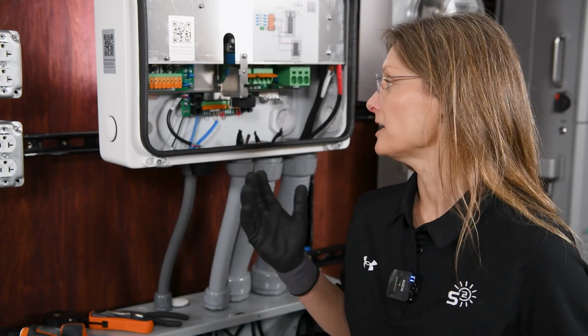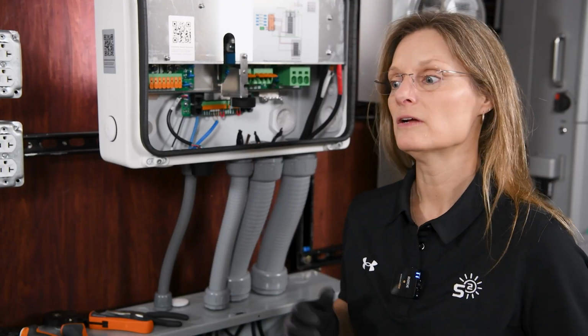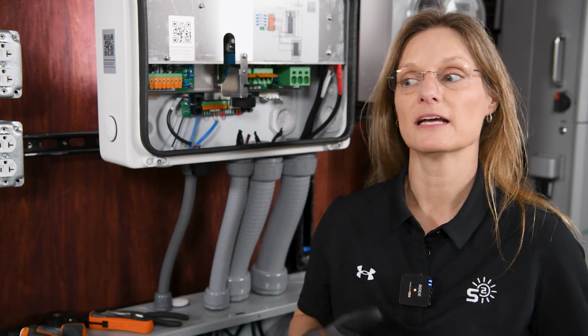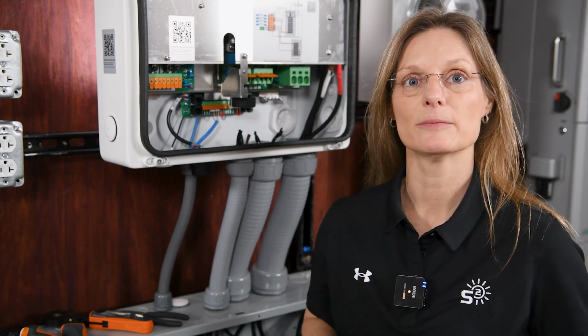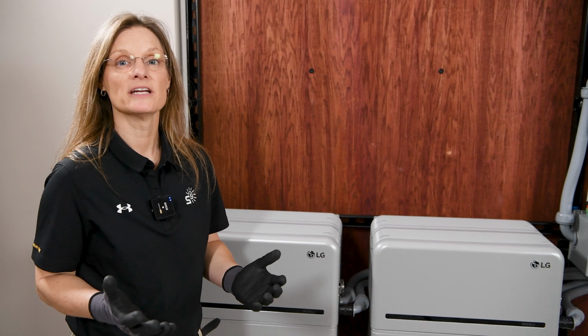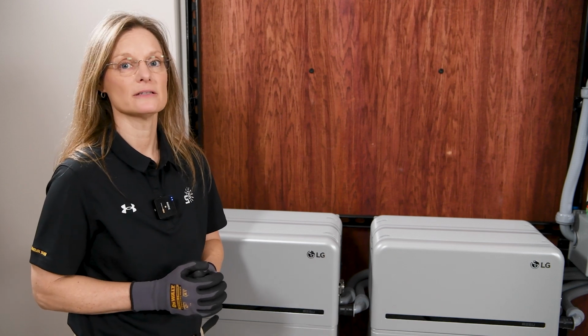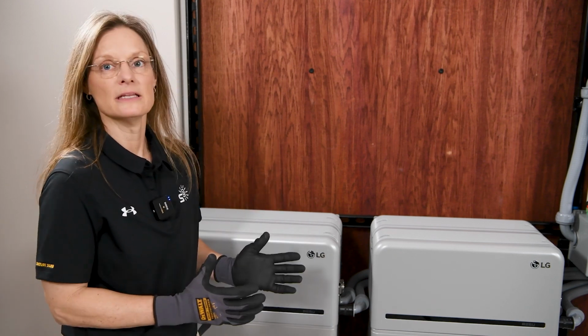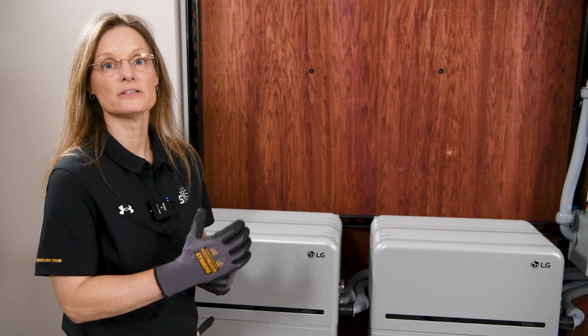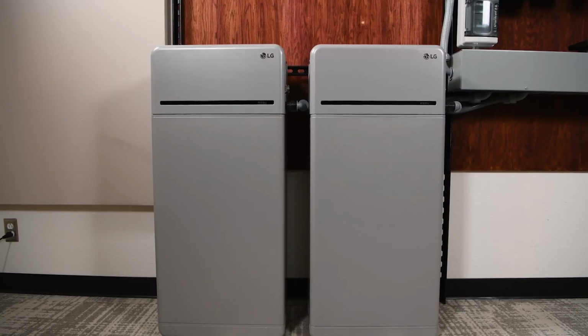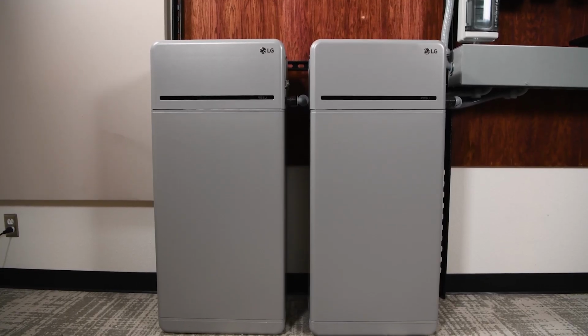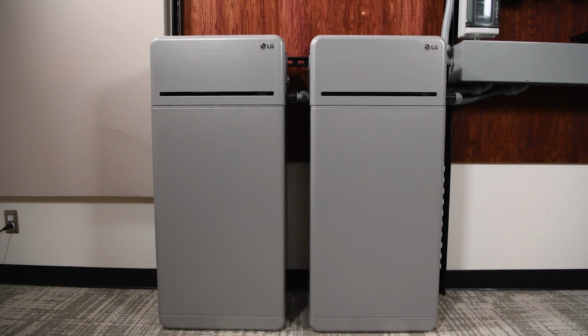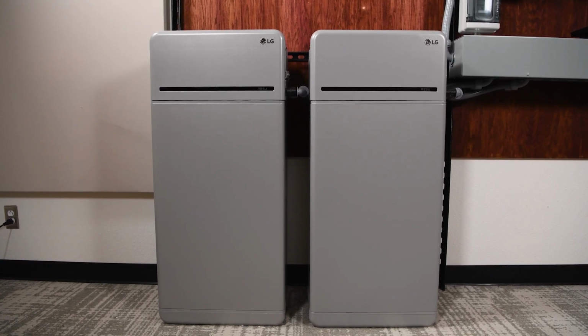Now that we've connected the communications inside our inverter, we'll move to our batteries and connect the communication cables there. Since we're connecting two batteries in parallel, we need to set them up in communication with each other and then with our inverter. The battery furthest from the inverter is typically the primary battery, and the one closest to the inverter is the secondary battery.